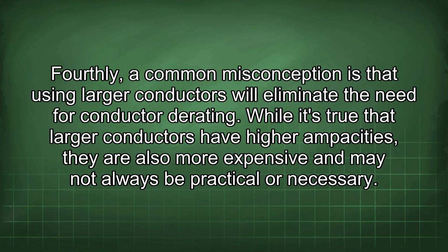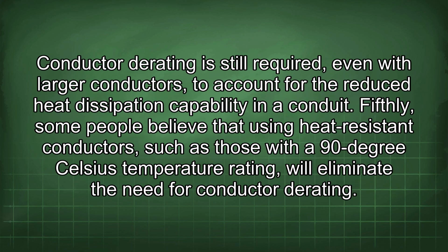Fourthly, a common misconception is that using larger conductors will eliminate the need for conductor derating. While it's true that larger conductors have higher ampacities, they are also more expensive and may not always be practical or necessary. Conductor derating is still required, even with larger conductors, to account for the reduced heat dissipation capability in a conduit.